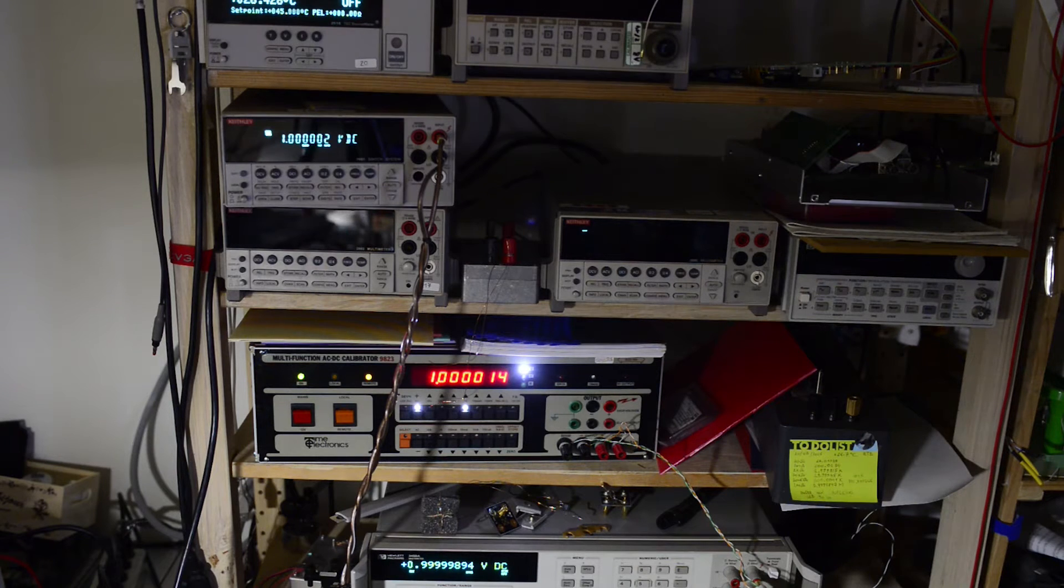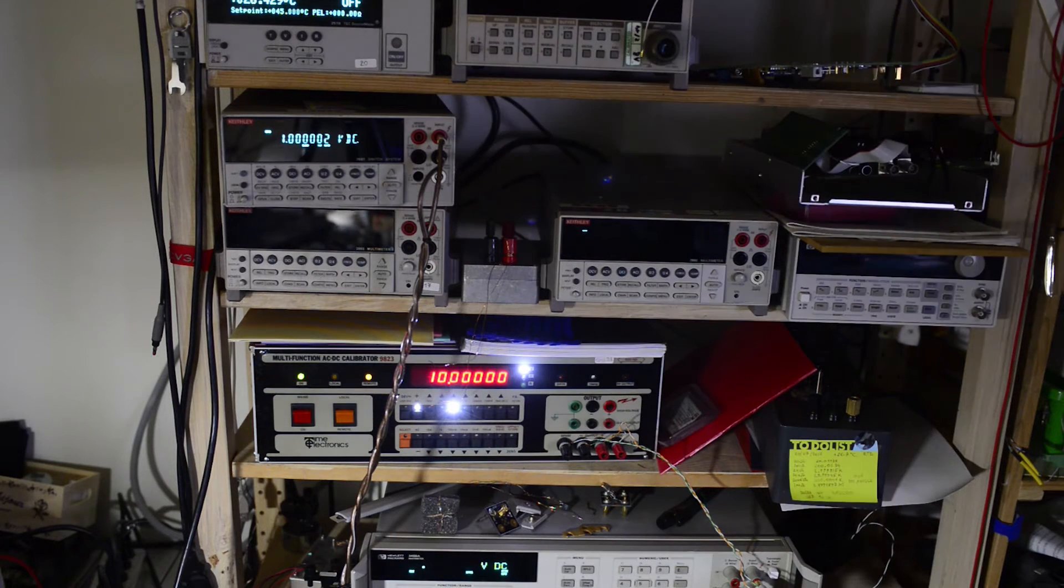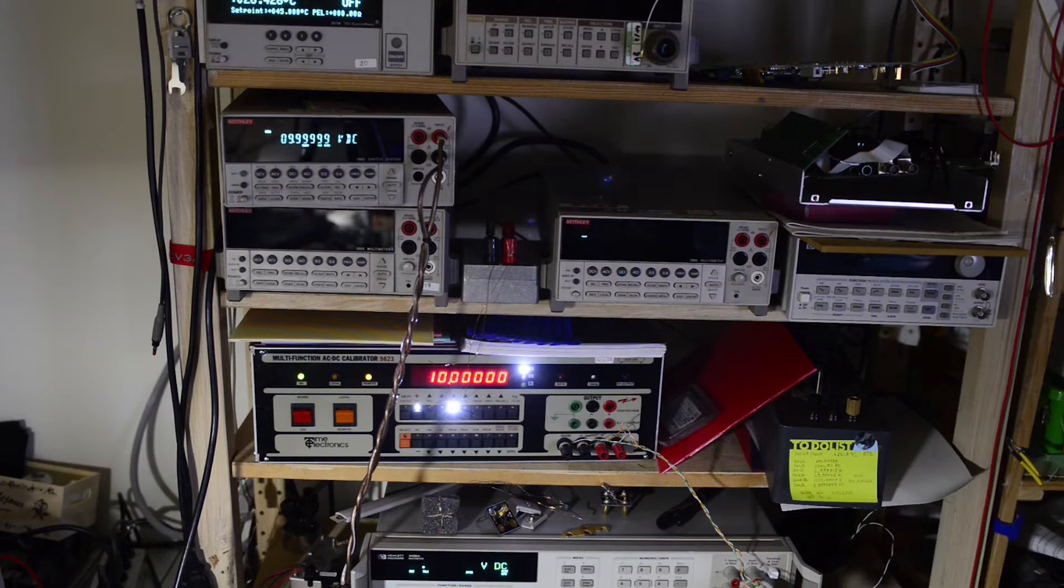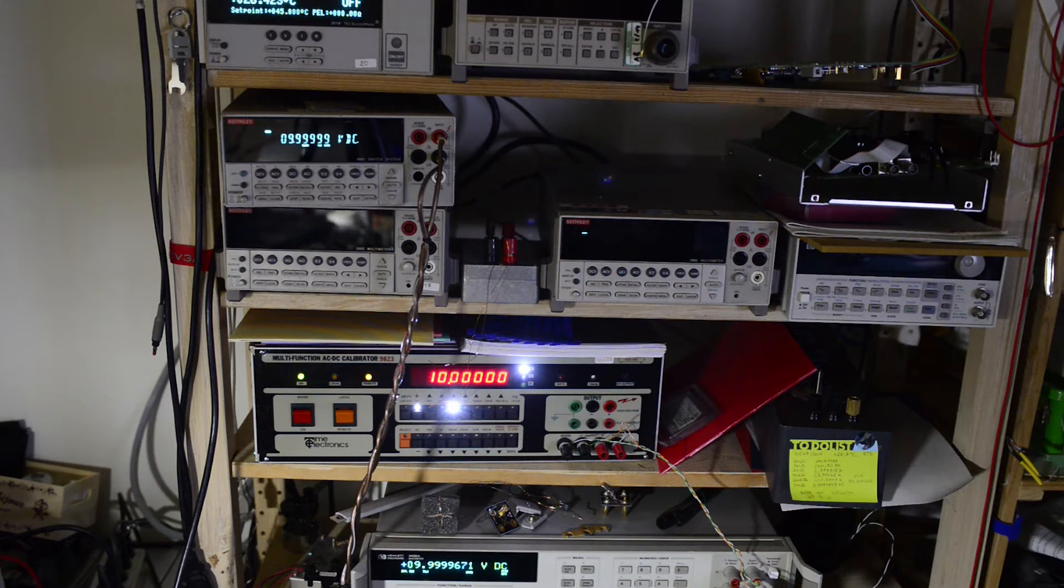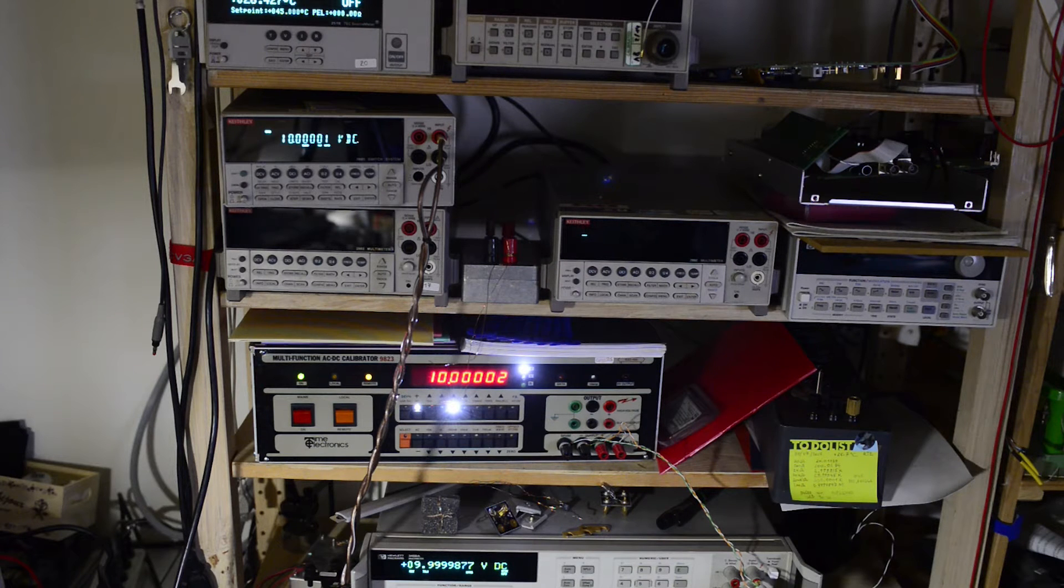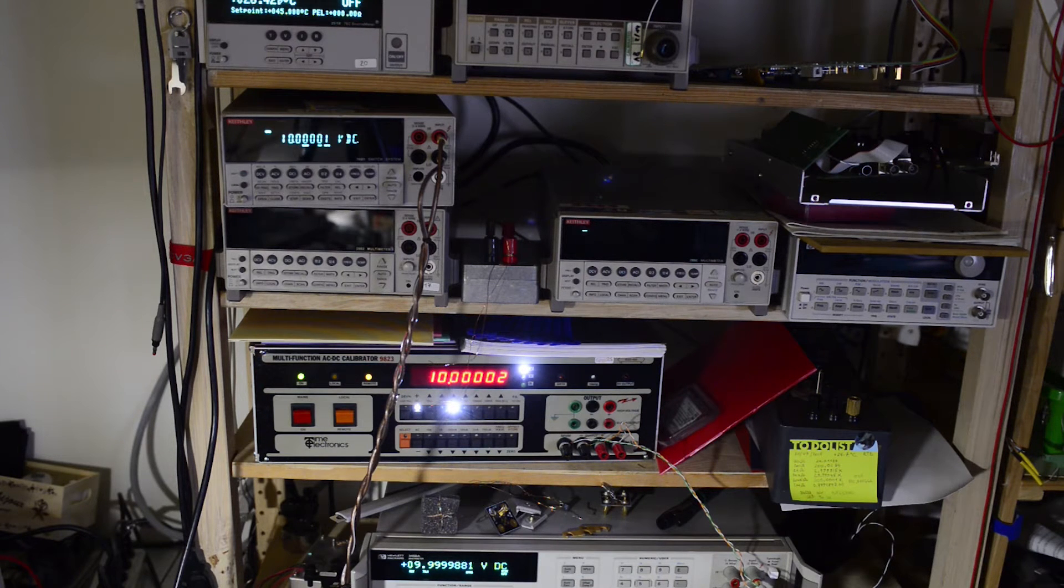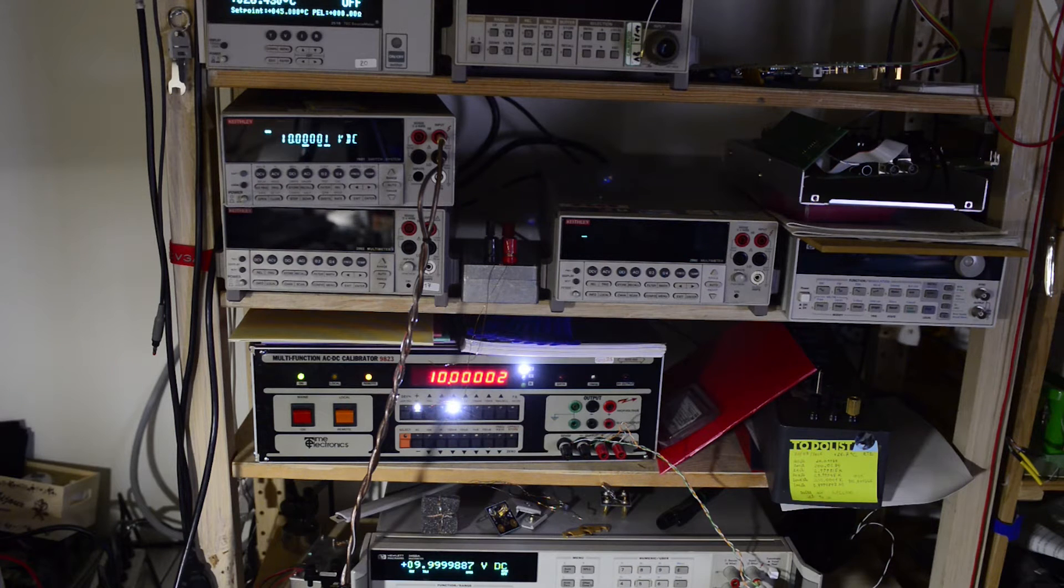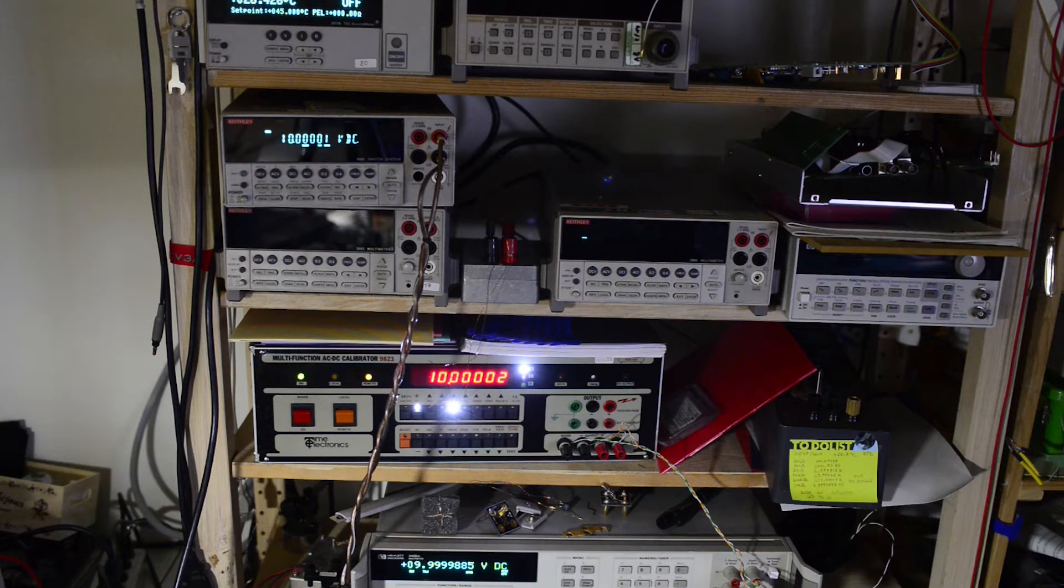And regarding the HP meter itself, I had it calibrated using LTZ1000 reference which gets shipped from another calibrated meter. Cross checks with my two other Keithley 2002 meters showed agreement within 10 ppm between all three of them.